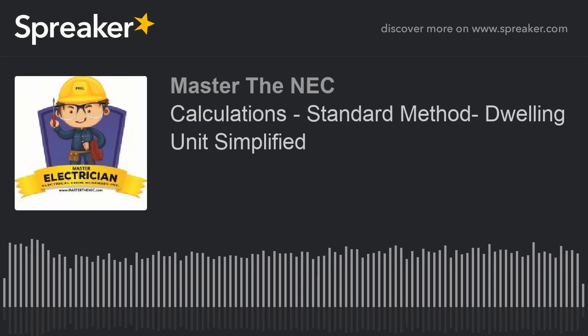I've got 3000 for the 2 small appliances. That was 1500 times 2. And then I've got 1500 times 1 for the laundry, so that's 1500. So that's 7500 plus 3000 plus 1500 for a total of 12,000 VA. That's where we're at so far.